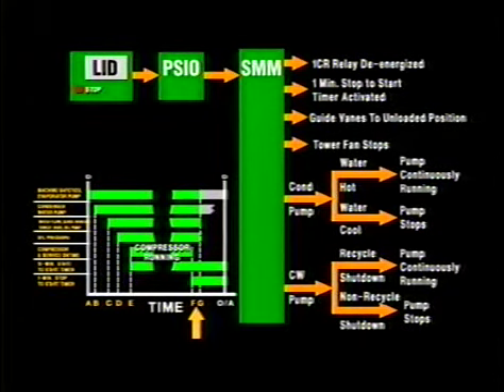The compressor will shut down when the chilled water temperature drops below set point. This is called a recycle shutdown. It will also shut down when an occupied time period expires, or when the stop key is depressed for at least 1 second, or when an alarm condition occurs. When any of these conditions occur, the compressor is shut down and the guide vanes are closed. The oil pump is shut off 1 minute after the compressor stops, and the condenser water pump is shut off when the condenser pressure drops to a predetermined level. The chilled water pump remains operating during a recycle shutdown to monitor the chilled water temperature for an increasing load. Otherwise, it is shut off at the same time as the oil pump.